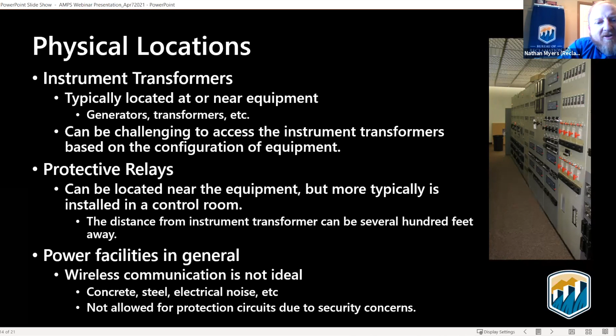The protective relays can be located near the equipment, but are more typically located within a control room. The distance between the instrument transformer and the control room may be several hundred feet away. So we can have a significant amount of wiring between the instrument transformer and the protective relays themselves. Our power facilities in general, when we look at solutions, wireless communication is not ideal. Our power facilities and dams are made out of concrete and steel, and they have quite a bit of electrical noise as well. And we can't use wireless communication for protection circuits due to security concerns.